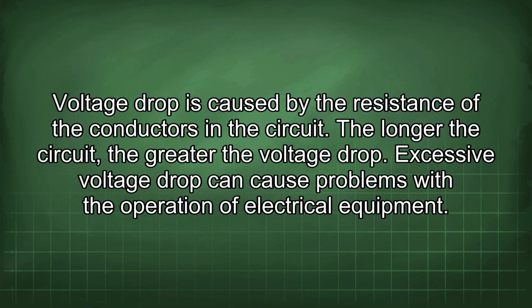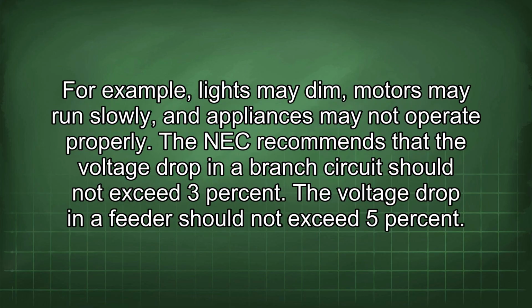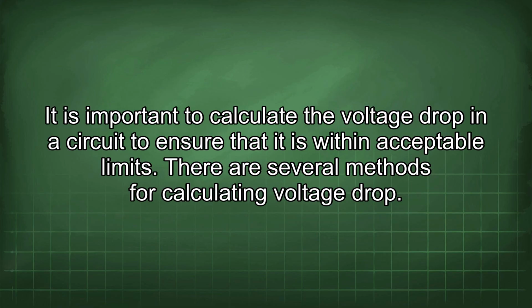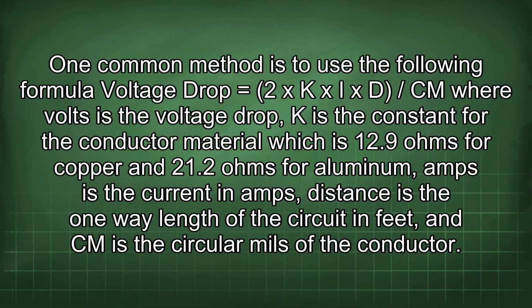Excessive voltage drop can cause problems with the operation of electrical equipment. For example, lights may dim, motors may run slowly, and appliances may not operate properly. The NEC recommends that the voltage drop in a branch circuit should not exceed 3%. The voltage drop in a feeder should not exceed 5%. It is important to calculate the voltage drop in a circuit to ensure that it is within acceptable limits. There are several methods for calculating voltage drop.